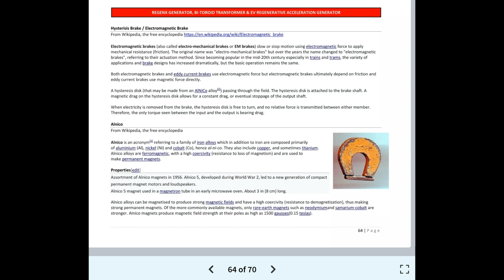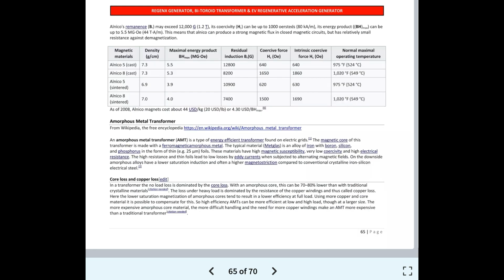Alnico remanence, B, may exceed 12,000 G, 1.2 T. Its coercivity, H, can be up to 1000 Oersteds, 80 kA/m, and its energy product, BH, can be up to 5 MGOe, 44 T·A/m. This means that Alnico can produce a strong magnetic flux in closed magnetic circuits, but has relatively small resistance against demagnetization. Amorphous metal transformer. An amorphous metal transformer, AMT, is a type of energy-efficient transformer found on electric grids.